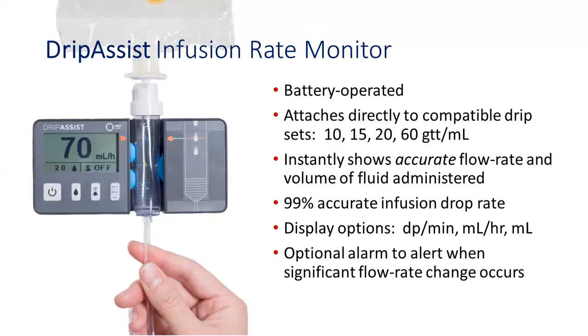So the infrared detection senses the drops, but the device has software on it. So there are algorithms on the device that take the drops and process that, eliminating any sort of light interference or potentially double drops. And so it kind of creates quality data out of the drop detection. So in laboratory testing, the device has been proven to be 99% accurate as a drop rate detector. So in counting drops, it's 99% accurate. As I mentioned, you can see drops per minute, milliliters per hour, or total volume administered in milliliters. There is also an optional alarm that will alert when there is a significant flow rate change. So unlike an infusion pump where you would initially dial in a rate, the DripAssist works a little bit differently.